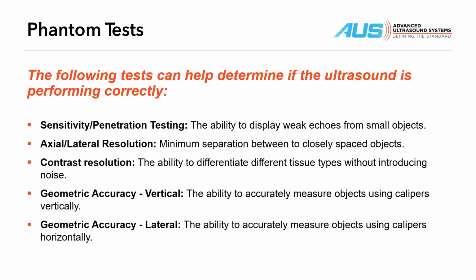So contrast resolution, sorry, is the ability to differentiate different tissue types, which is different tissue densities, without introducing noise. Geometric accuracy, vertical and lateral. You want to use your calipers to measure objects on your phantom so that you can ensure that the accuracy of your caliper measurements is within tolerance. There are tolerances if you're accredited, but if you're not accredited, it still gives you an indication of how your ultrasound system calipers are measuring. So we'll go over these tests and define them over the next couple minutes.